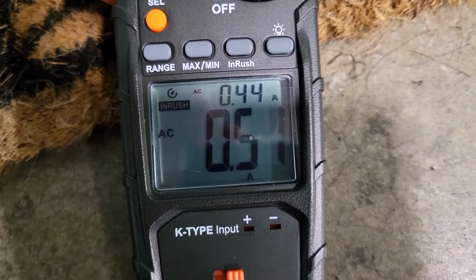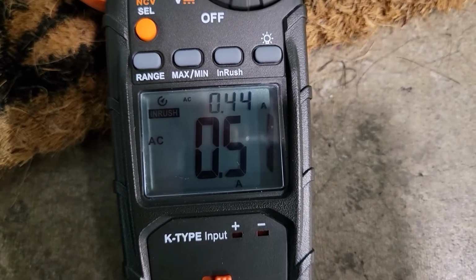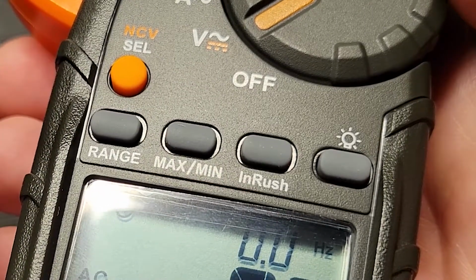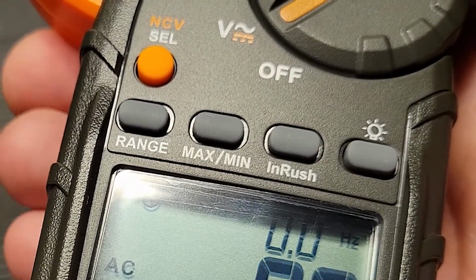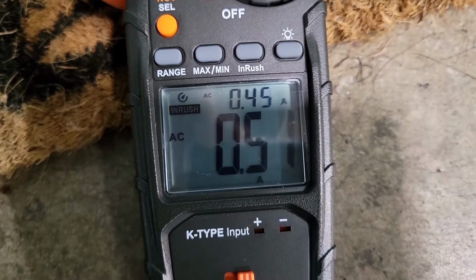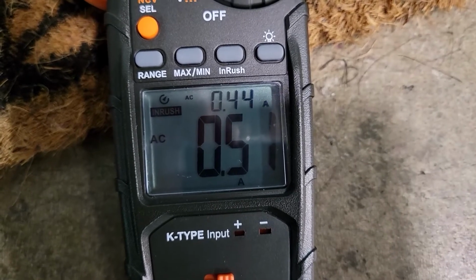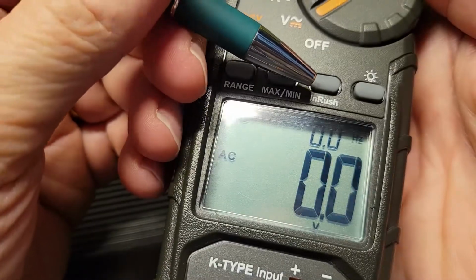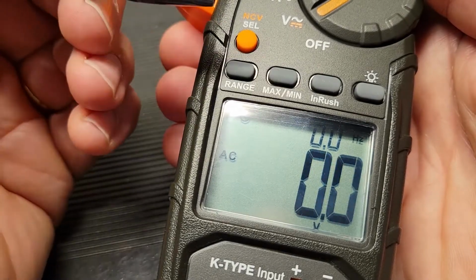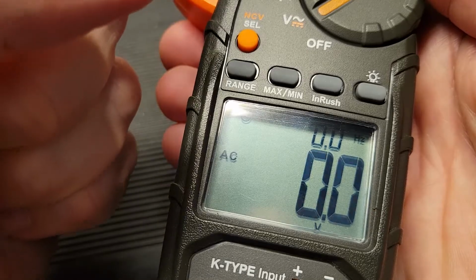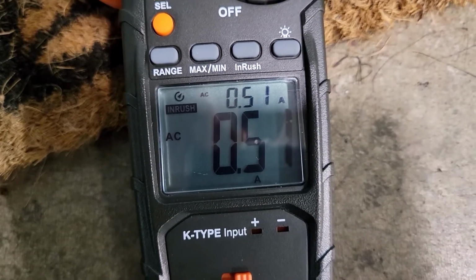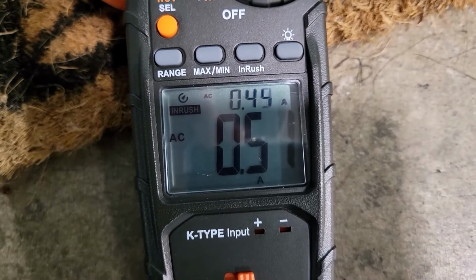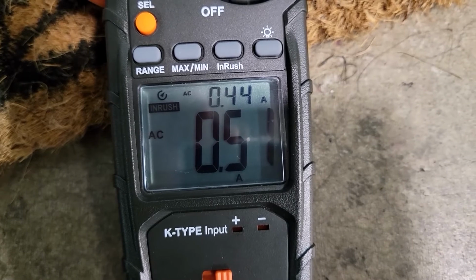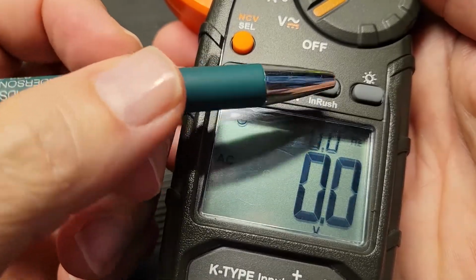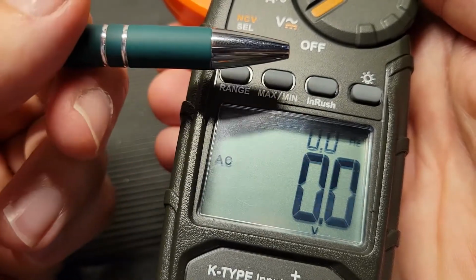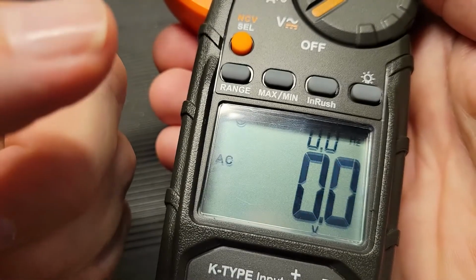So that's why this is called an HVAC digital clamp meter, because that is a function more probably used by the HVAC industry where there are lots of compressors and motors. It'll measure that inrush, which is usually very short, and most meters would just go through it and come back out, and you'd have that average reading. So this records it. It's a little bit different than max and min, where the inrush is just looking at that instantaneous increase of current that's coming through the unit, records that, then shows you the rest of what it's doing, the current as it drops down. So it holds onto that briefly so that you can see that inrush. A little different than max and minimum, where it holds a high value and a low value.